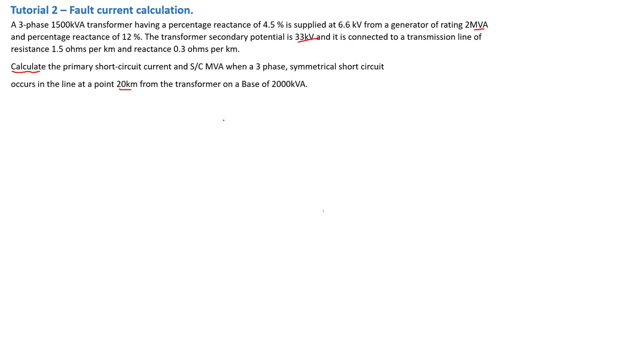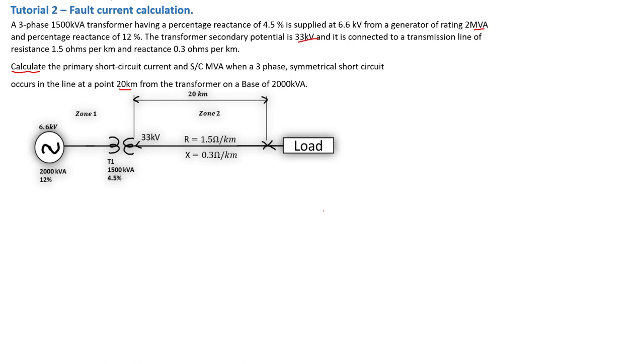The first thing to do is draw the schematic to illustrate the problem. We have a 6.6 kV generator at 2 MVA with 12% percentage reactance, connected to a step-up transformer going from 6.6 kV to 33 kV for the transmission line. The fault occurs at the 20 kilometer point. We need to calculate the short circuit current and short circuit MVA at that point.